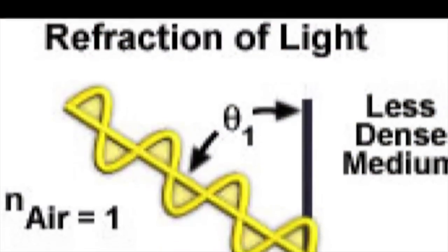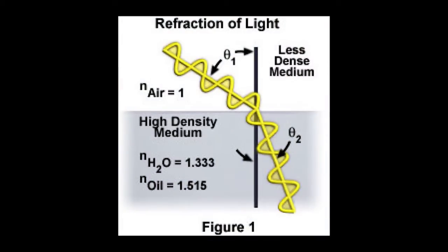When we're using light in a microscope, the light can be refracted by the different mediums that it goes through. For example, when light transitions from air to glass, it is refracted or bent based on the density of the glass. So the light is going to be refracted by the cover slip. It's going to be again refracted by the mounting medium around the specimen. It's also going to be refracted by the specimen, and it'll be refracted by the slide itself. If you use immersion fluid between the objective and the cover slip, the light will also be refracted by that immersion fluid. So it's important to remember that light is being bent by everything you're putting it through, and so you must use the proper materials to get the highest resolution out of the objective.